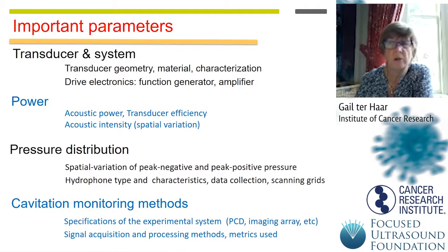We'd like to know the spatial variation of the pressure field as well, with peak positive and peak negative pressures being listed. And how is that measured? What sort of hydrophones are being used? What are their characteristics? How's the data being collected? And how is the scanning done? At what spatial resolution, for example?